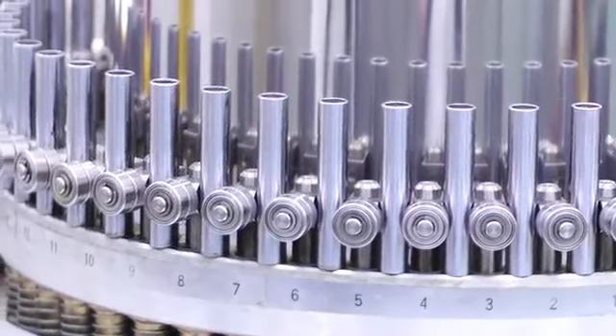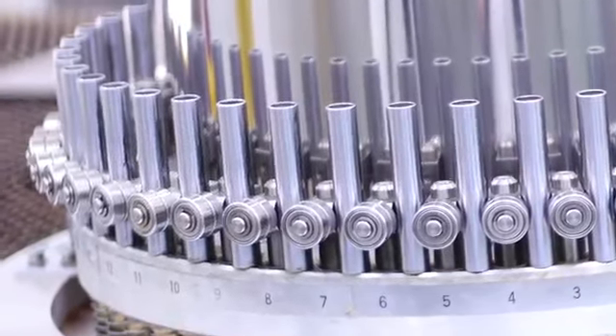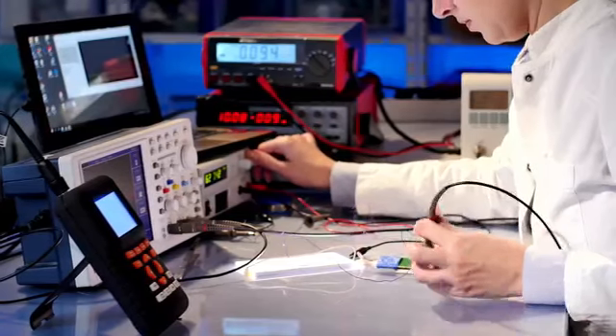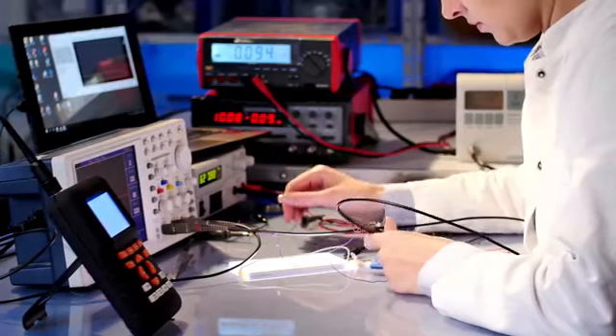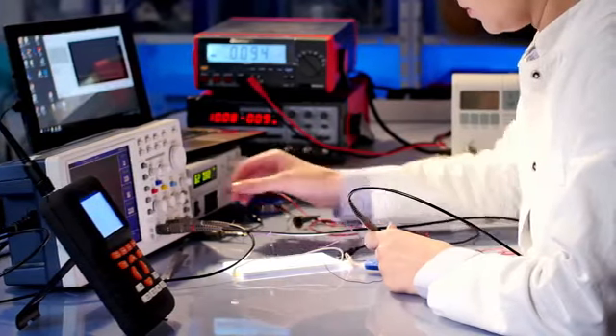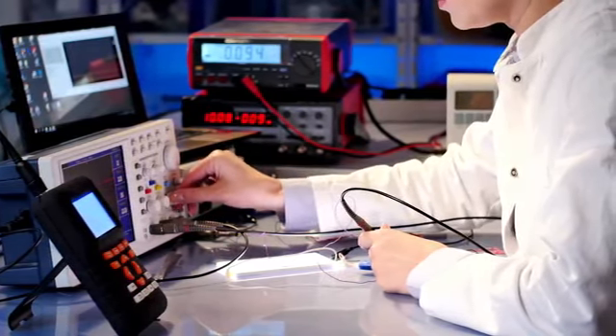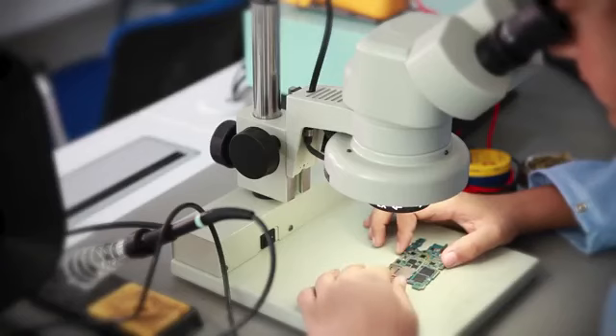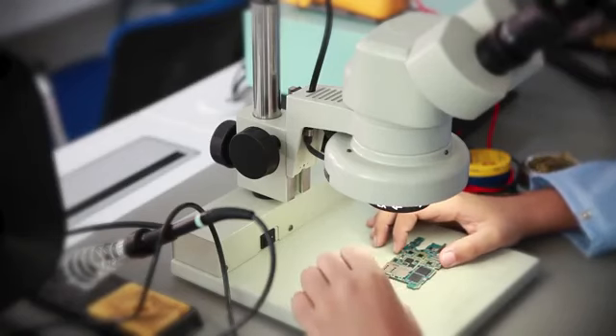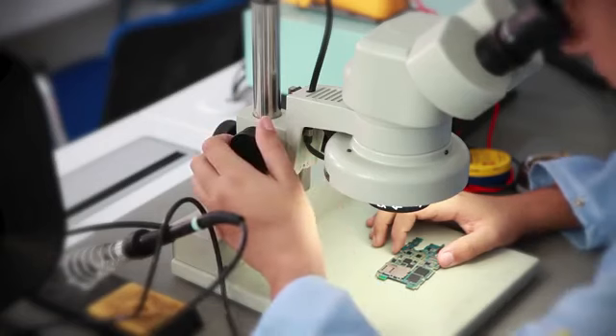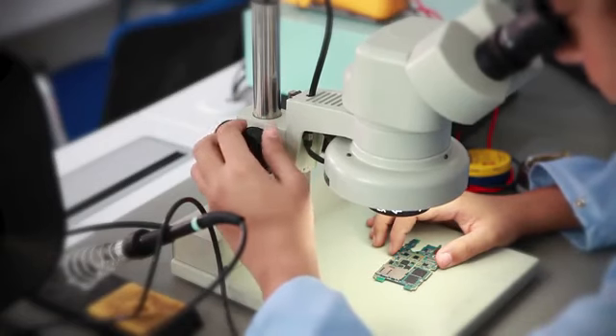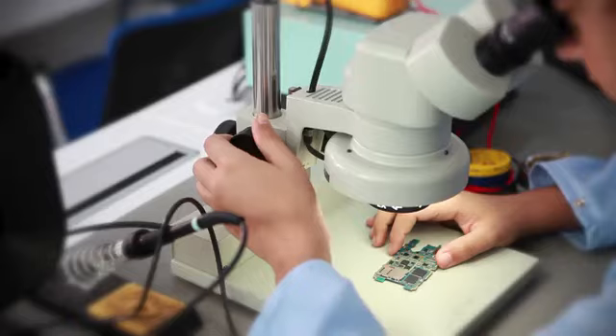17025 impacts the results delivered by laboratories in a number of ways. The standard requires them to meet criteria for the competence of their personnel, the calibration and maintenance of their equipment, and the overall processes they use to generate the data. So the impact is quite significant in that it requires the laboratory to think and operate in a way that ensures that their processes are under control and that the data are reliable.